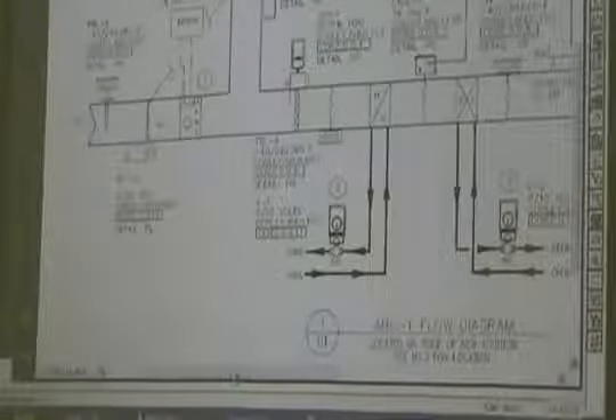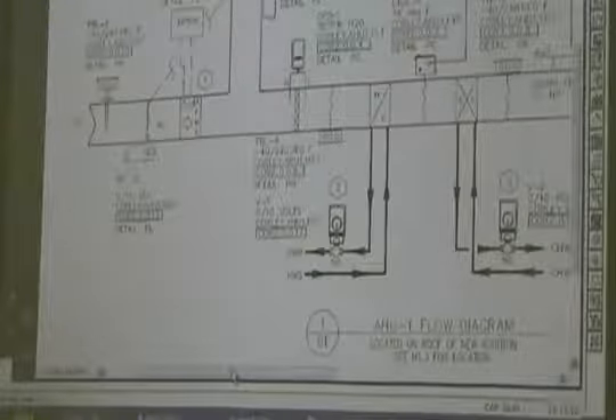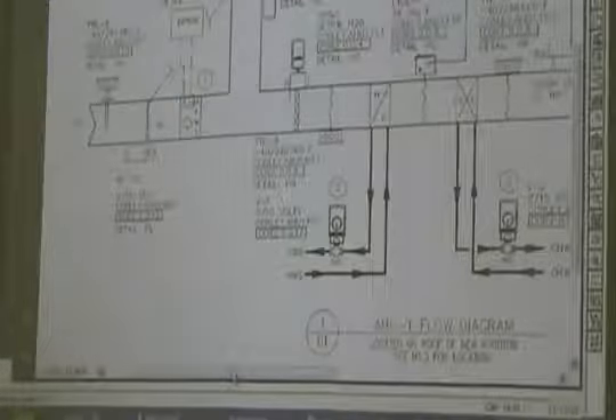Depends on what time of year it is. Okay, what would be the smart switchover point? 75, 72. Why? Because that's probably what our return air is. Okay, so we have this other temp sensor up here on the return. We know what the return is all the time. We know what we're measuring the outdoor air. So we're going to compare the two. And if the outdoor air is cooler than the return air, anytime that's the case, we're going to use outdoor air instead of return air. That's called just a simple dry bulb switchover to what we would call in the South our economizer mode.